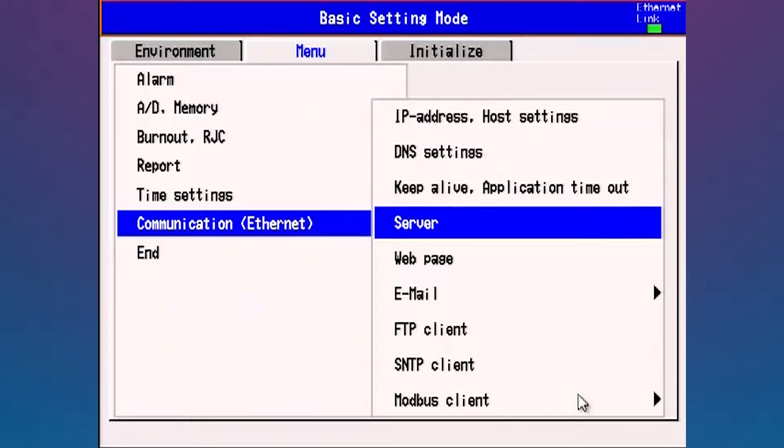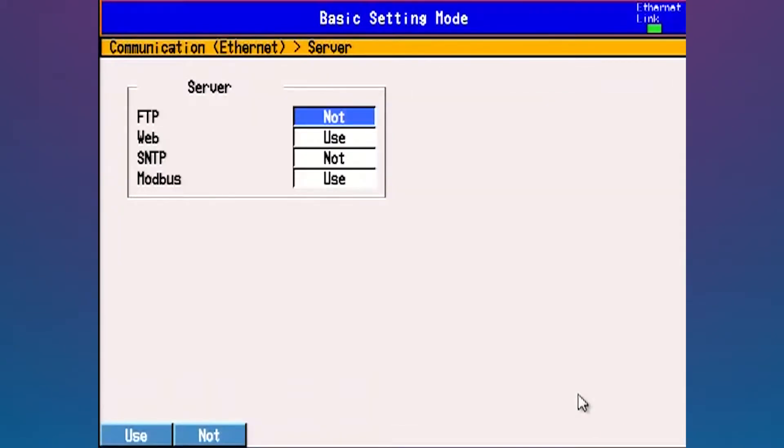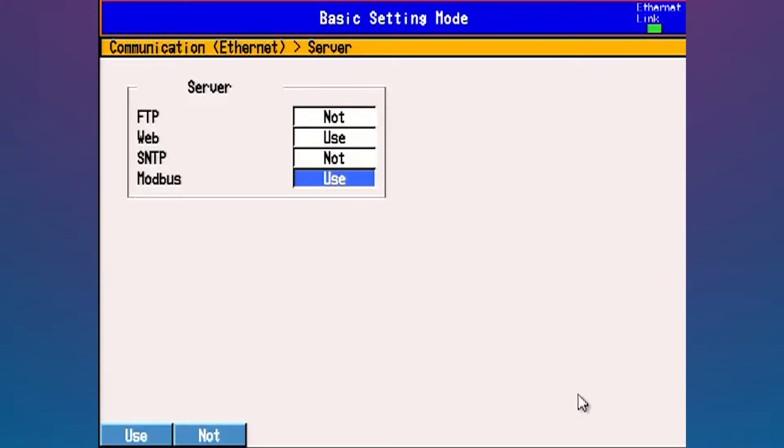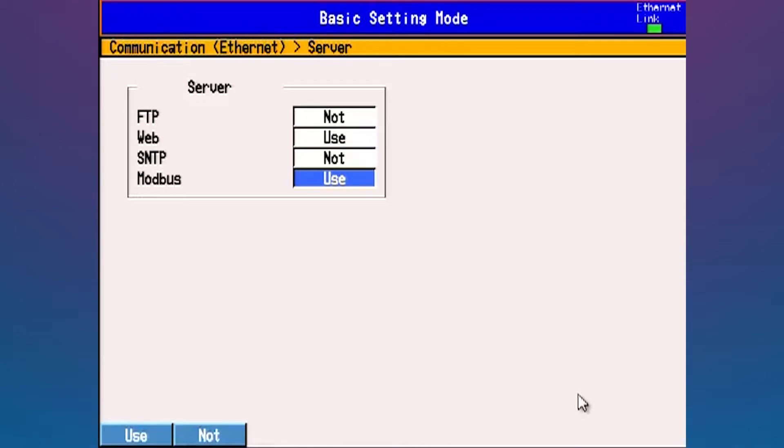The next place I'm going to need to go to is server. I go to server, hit the display enter key, and go down here and hit the function key under use. You need use for Modbus in order to allow Modbus communications to happen. Then once again, hit the display enter key to make sure that you've accepted that change.